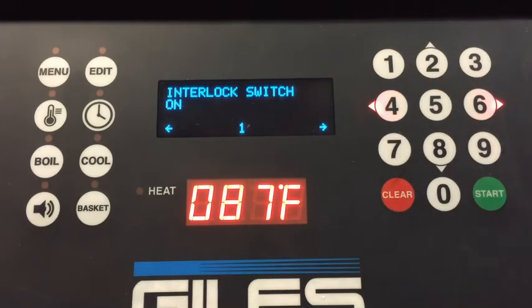Interlock switch, that's where you get that power failure when you first turn the unit on. If you turn that off, you won't get that. It'll go directly into heating and all. We like the interlock start because if you have a power outage, it does take someone else to go ahead and push that start button before that unit will start heating up again. That's great if you have a place that comes up with low voltage. It'll save on your contactors, and it's a safety factor. Now we know that someone is aware that this fryer is turned back on.